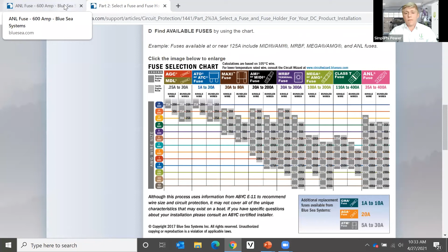But let's just say you picked an ANL fuse and you want to see how long it's going to take to pop. Because a common misconception is: let's say I've got 2 batteries rated to 37.5 amps each, that's 75 amps, so I want a 75 amp fuse. It's not always correct. If you're using a 75 amp fuse that doesn't blow until it's got about 140% of its rated current, then that 75 amp fuse is not going to blow until you've reached 105 amps.